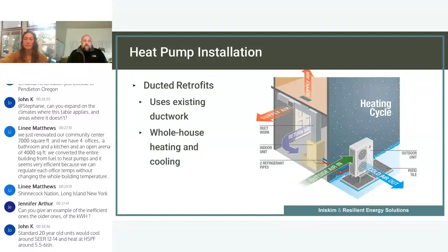Next slide, please, Steph. So here we've got a picture of a natural gas furnace retrofitted with a heat pump. This particular heat pump is vertically oriented, meaning that it draws the air from underneath and moves it straight up, drawing the return air from the side and up. Because it's that way, as you can see in the picture, they had to rework the ducting to build out underneath of the heat pump, and also along the side, they had to widen the duct because the air is actually having to make a 180-degree turn. It's going down and it has to turn once and then turn back up into the furnace.